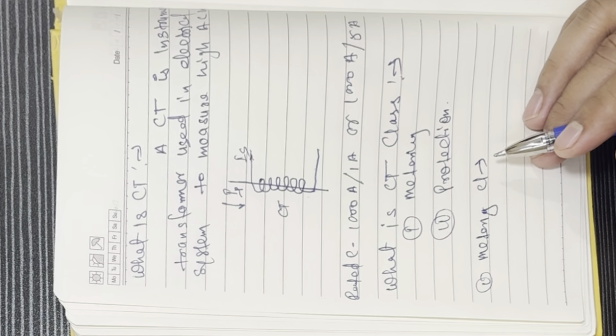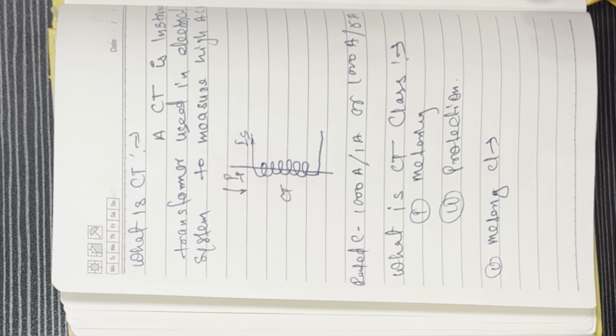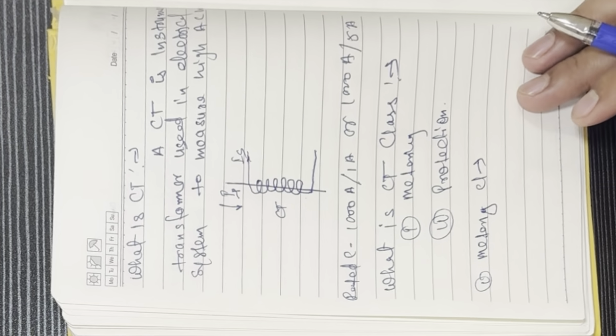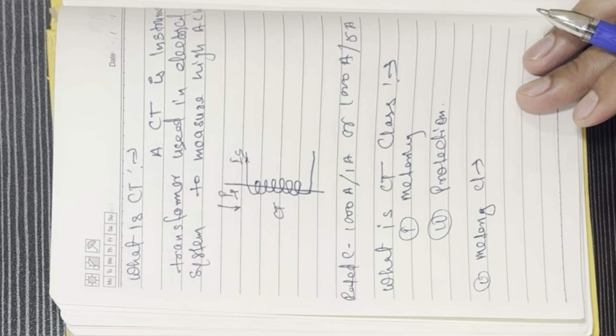Normally the load varies depending upon the load requirement. Suppose the CT is installed in a solar PV plant. In the morning the power rating will be less because of the generation. Over time it will increase, and it will be at the top during the peak hours. It will not be constant 100% all the time. It will vary from 5 to 120%. In these scenarios we need a CT with a high accuracy class to measure with less error.